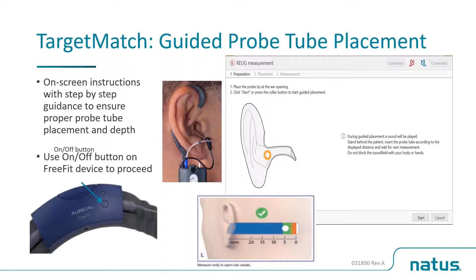So what does that look like on the screen? You can actually view the REUG, or the real ear unaided gain response, as well as this guided measurement here on the side. When you see a number here, this is basically telling you how many more millimeters is recommended for you to push the probe tube into the ear. What they're doing through this process is looking at the natural resonant peak as well as the negative deflection on the unaided gain response.